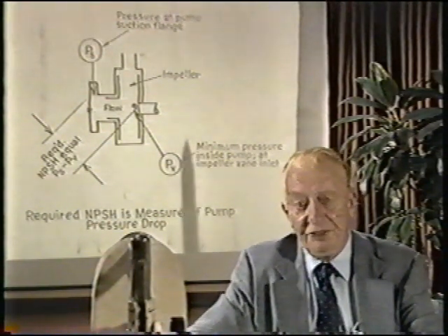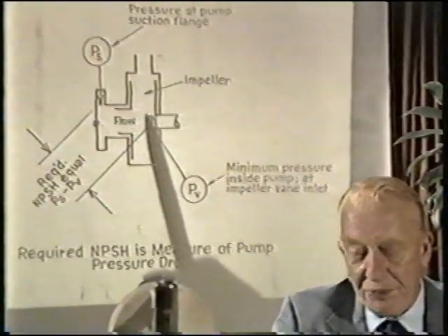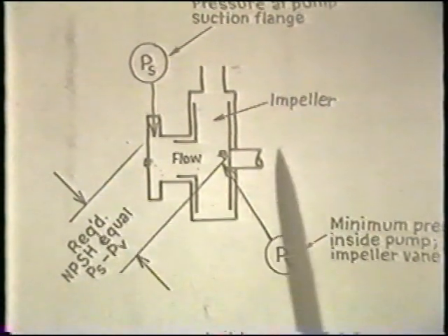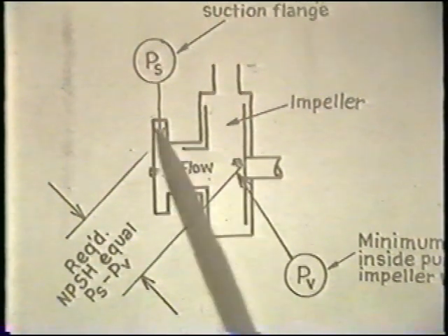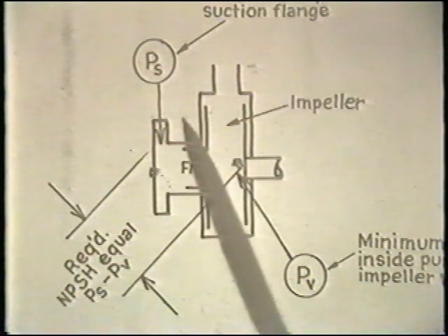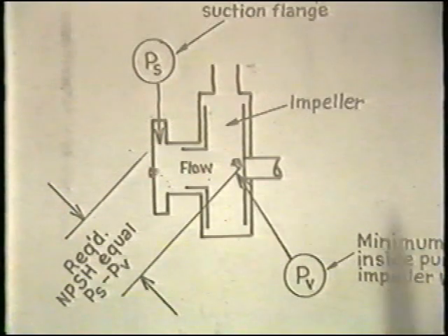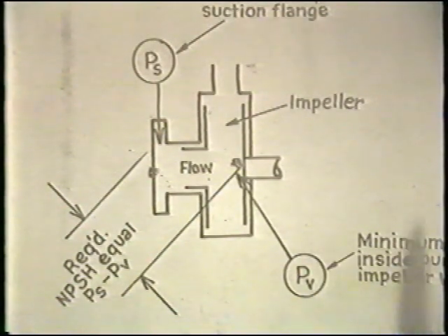So let's define again the problem. We have a pressure drop from the pump suction to the inside of the pump. If that pressure drop exceeds the pressure available at the suction flange over and above the liquid boiling point, we will flash inside the pump, causing the problems described.